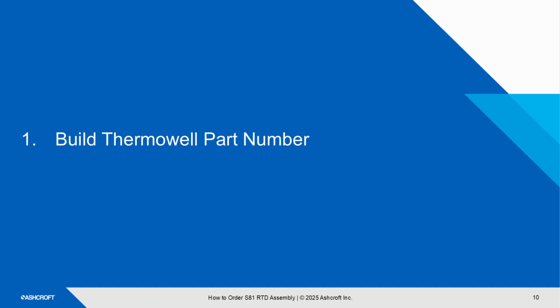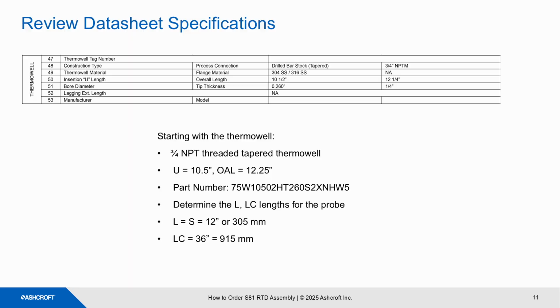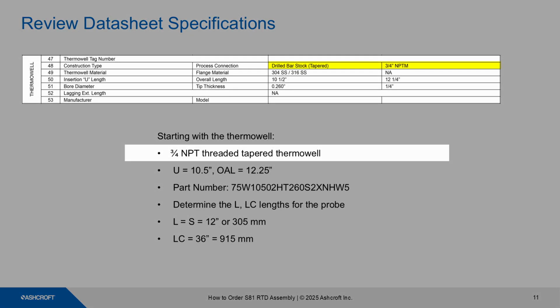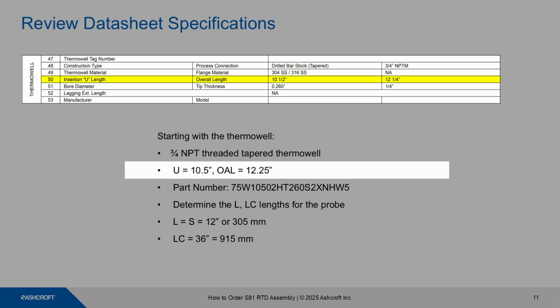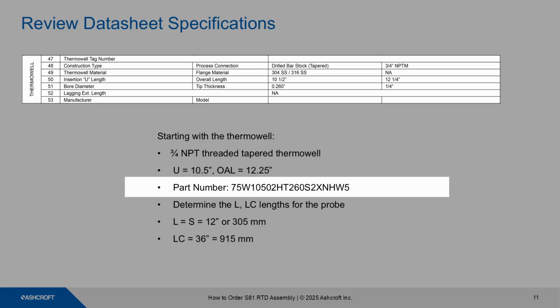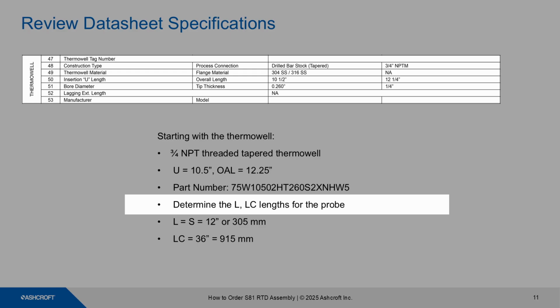Now we're ready to build the thermowell part number, the first of 3 part numbers that I will be walking you through today. We've reviewed the ISA data sheet, so we know that the requirement is a 3/4 inch NPT tapered threaded thermowell. It has a U dimension of 10.5 inches and an overall length of 12.25 inches. We look at the Ashcroft data sheet for the threaded thermowell, and we come up with a part number of 75W10502HT260S2XNHW5.